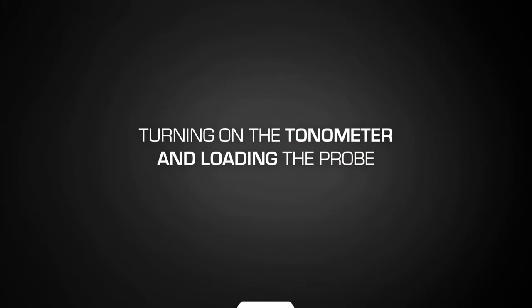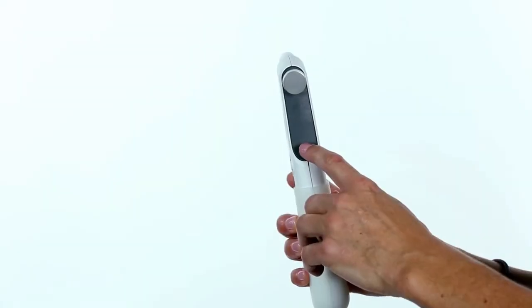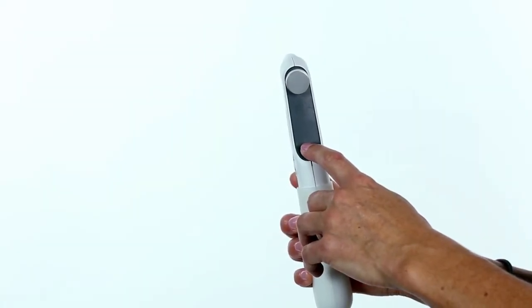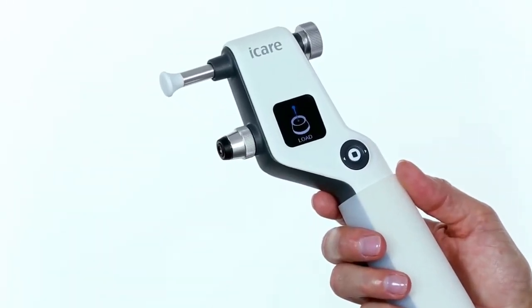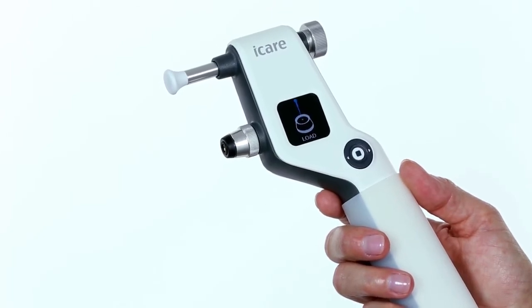Turning on the tonometer and loading the probe. To turn on the tonometer, press and hold the measure button for three seconds or until you hear a beep. Load the probe into the tonometer when the display screen shows Load Probe.